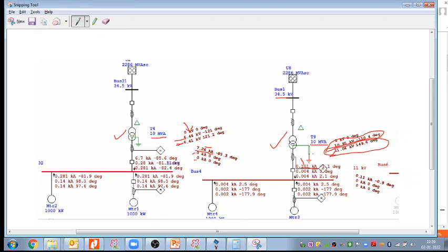Second point, we have to use NGR type system earthing here. How much current do I want to allow here, or how many ohms do we want to put here? The allowable current I have taken is 100 ampere here, but how much allowable current through the NGR, this allowable current we have to decide.